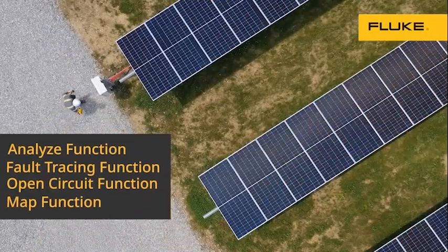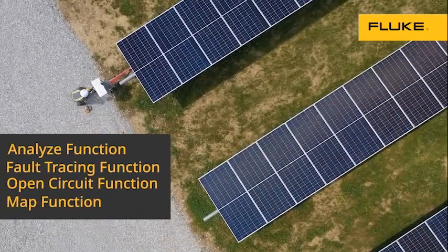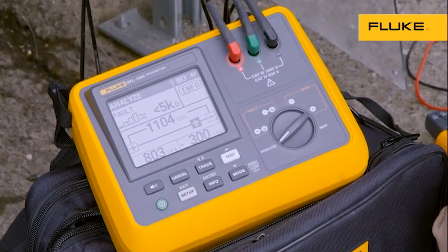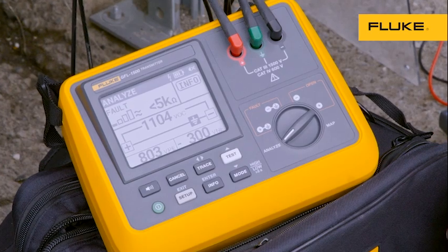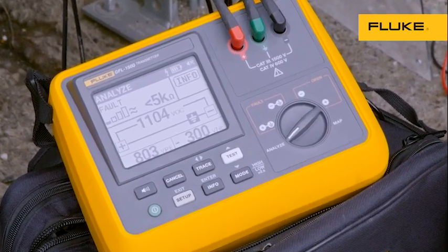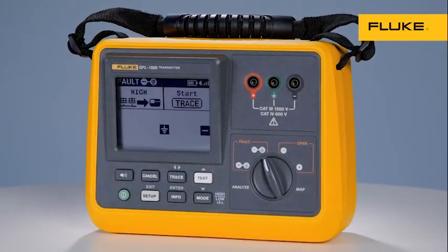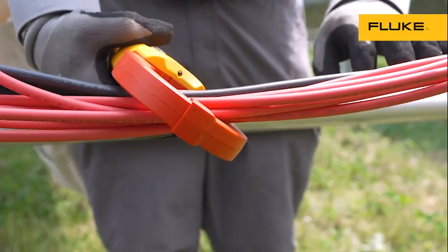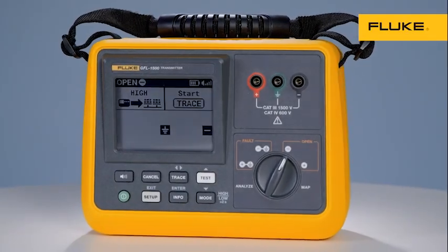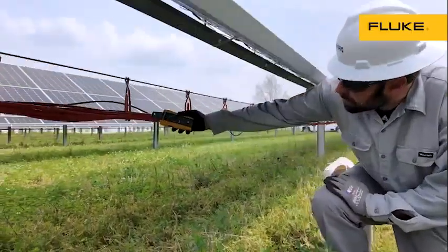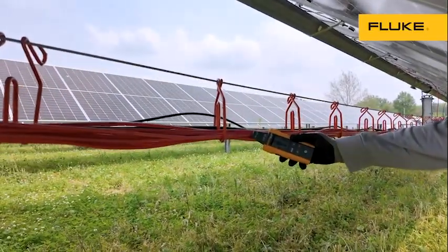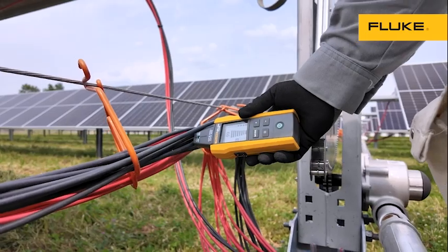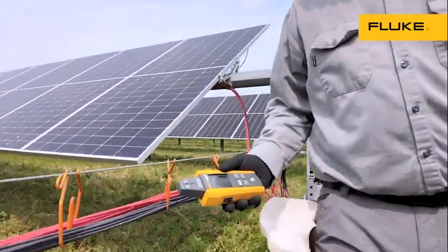You have 4 different functions to troubleshoot your array. Analyze function lets you quickly identify the presence of an active fault with key diagnostic details. Fault tracing function guides you along the fault path to pinpoint the failure in the array. Open circuit function helps you locate breaks in wires and guides you directly to the point of interruption. And map function helps to identify and confirm string layouts by routing the traceable signal through a healthy string.